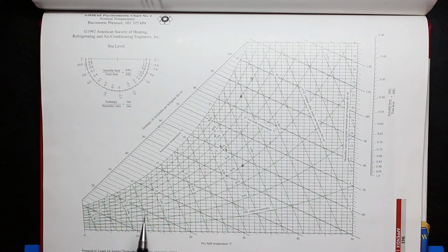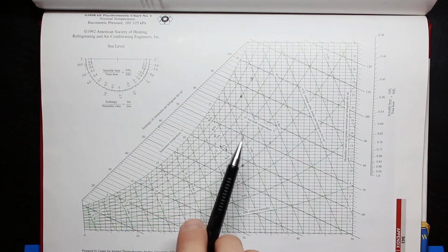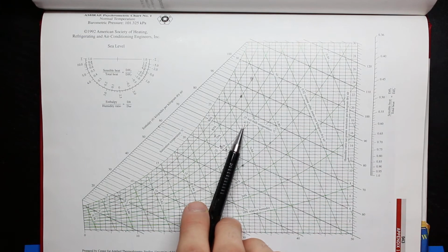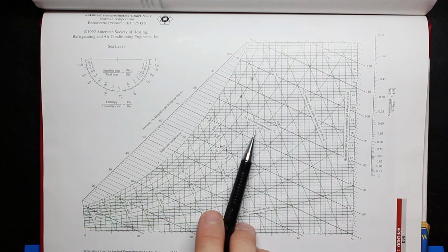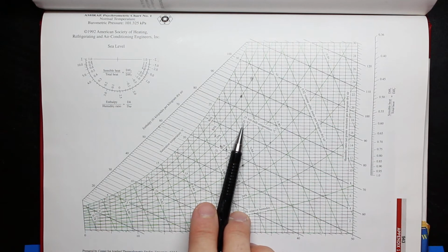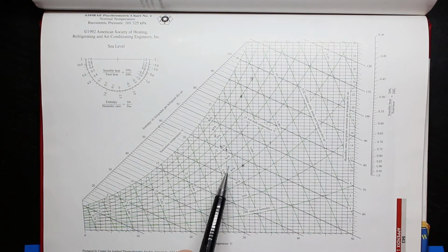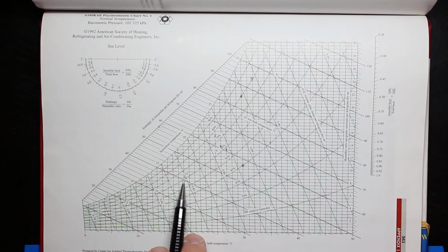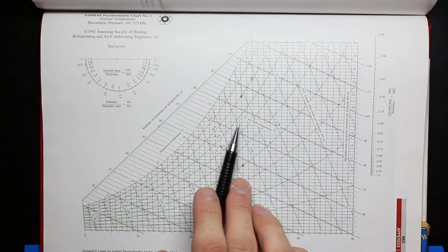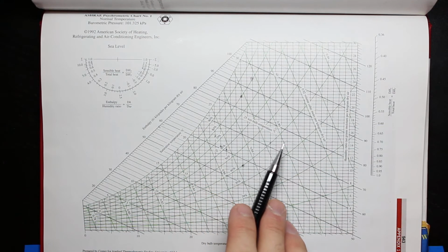What else? The other thing is, you see here it says wet bulb temperature. So these lines are the orientation of the wet bulb temperature. For this particular one, I'm pointing at 25 degrees C wet bulb temperature. The other wet bulb temperature line that I have is here, 20 degrees C wet bulb temperature, and 15. So the wet bulb temperatures are shown with dashed lines.